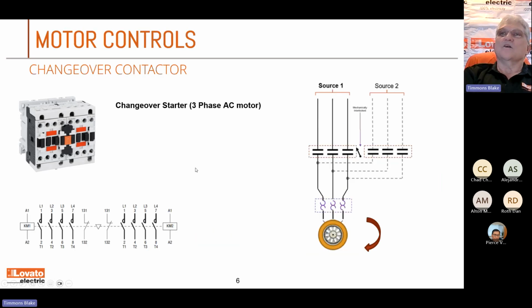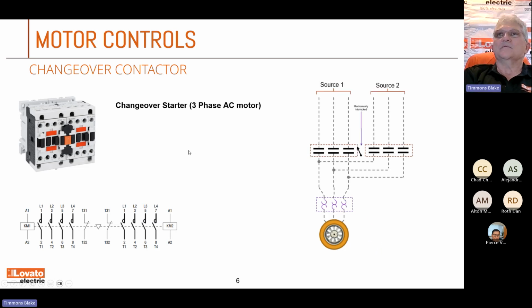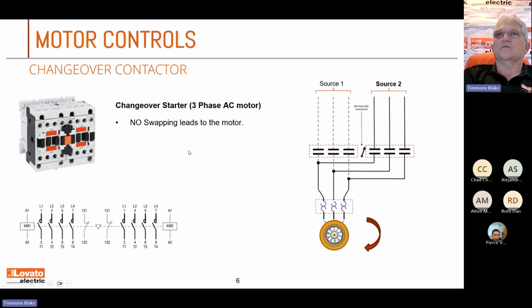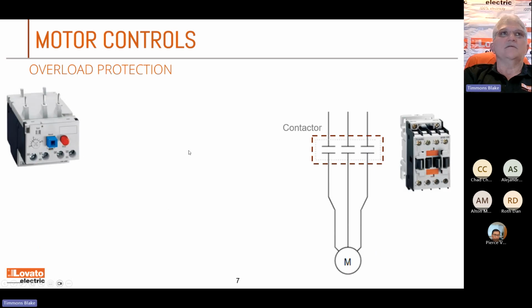Okay. You also have a changeover contactor. Works a little different, but you don't really reverse the lead. You just have two different sources coming in. You see how it works? Yeah. There it is. Turn it over. You don't swap the leads. Mechanical interlock. Good. Now let's talk about the overload protection.